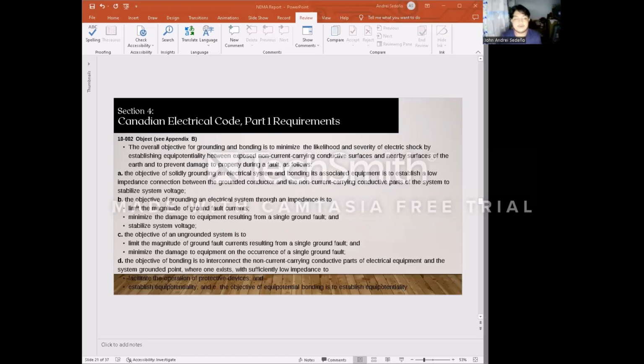Now, the overall objective of grounding and bonding is to minimize the likelihood and severity of electrical shock by establishing equipotential between exposed non-current-carrying conductive surfaces and nearby surfaces of the earth, and to prevent damage to property during a fault. The objective of solidly grounding an electrical system and bonding its associated equipment is to establish a low impedance connection between the ground conductor and the non-current-carrying conductive parts of the system to stabilize the system voltage.